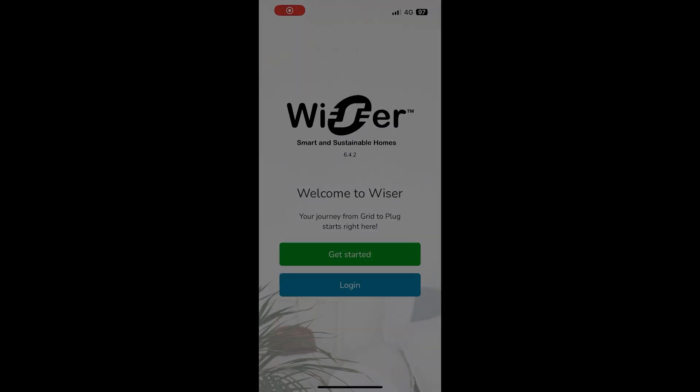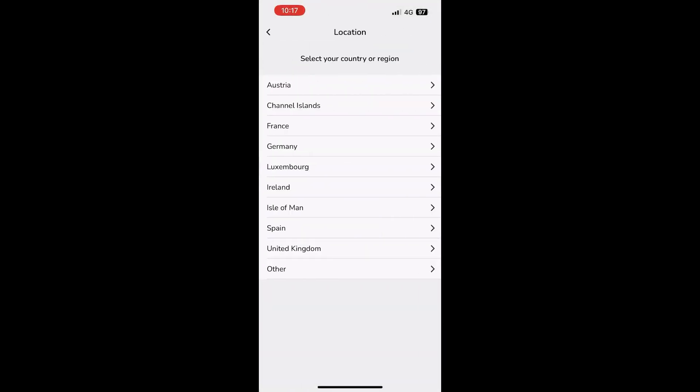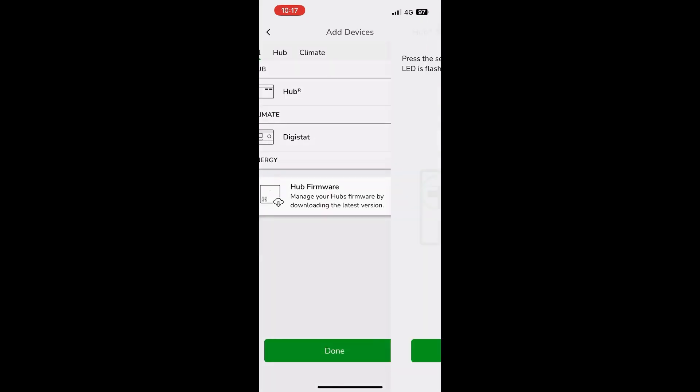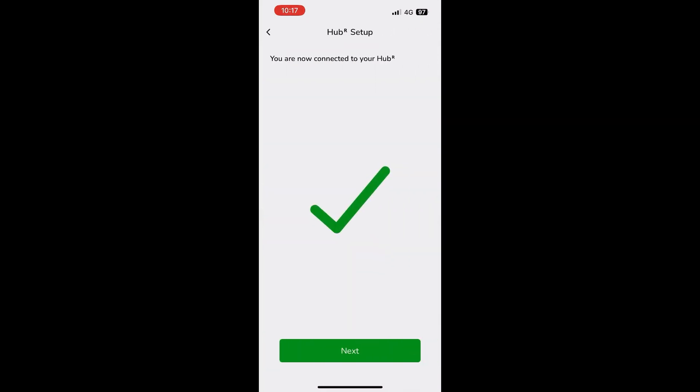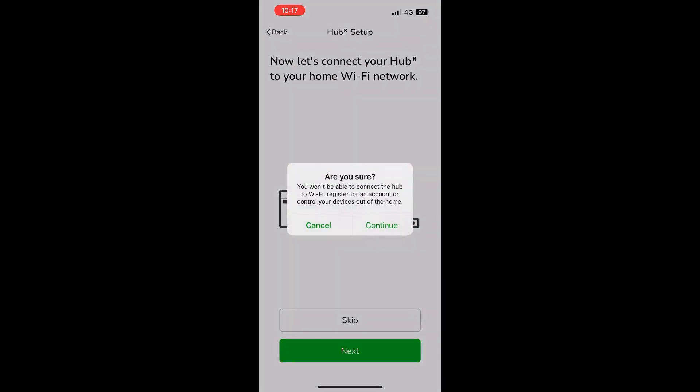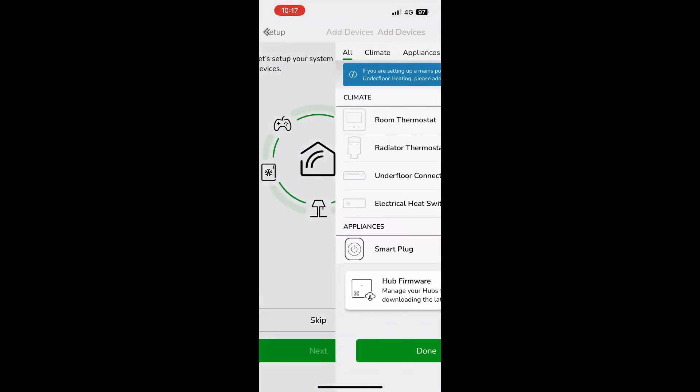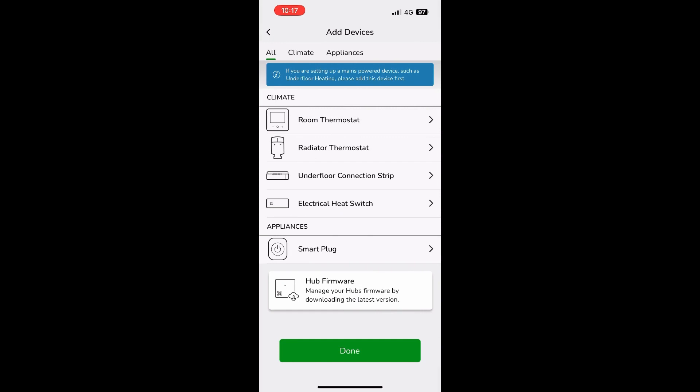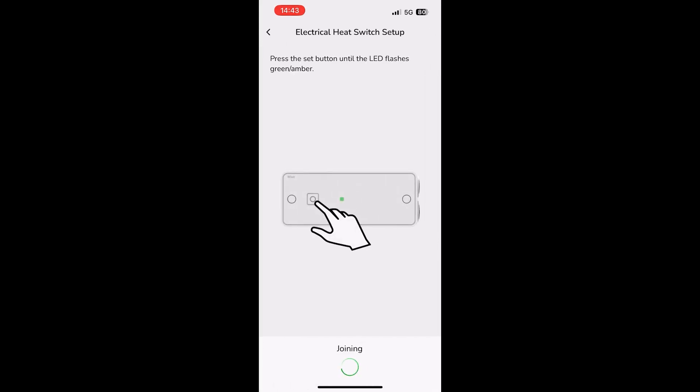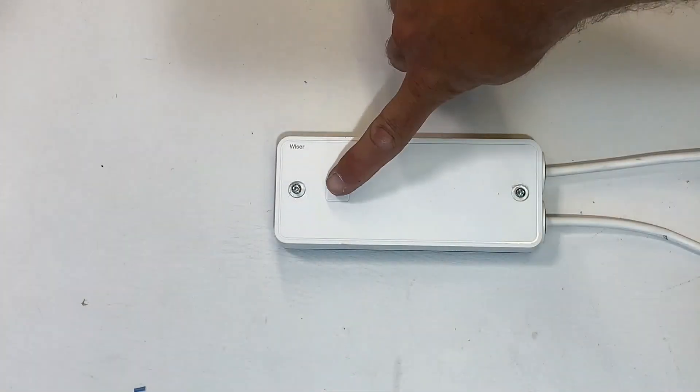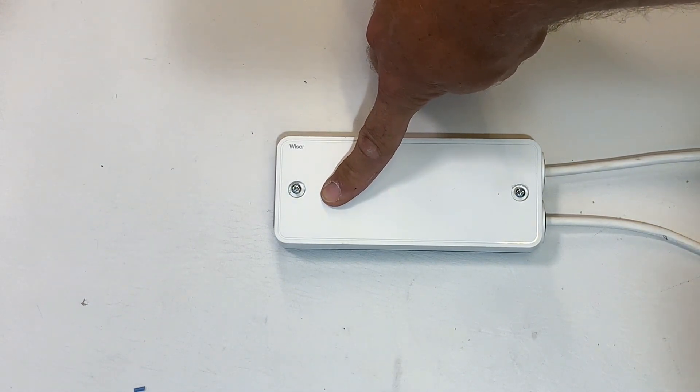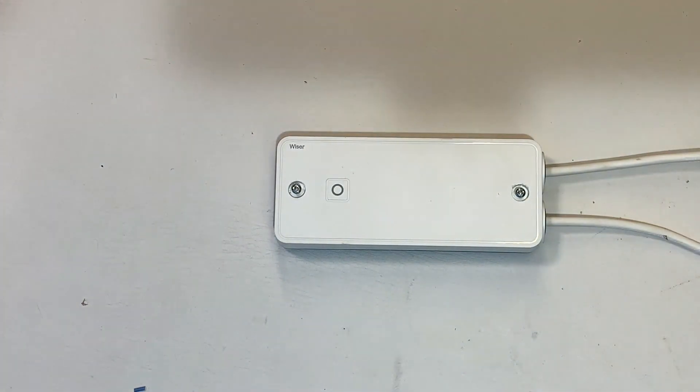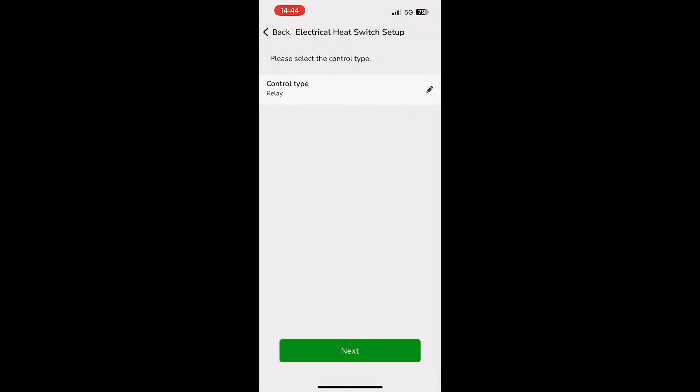Launch the Wiser Home app and click get started. Follow the professional installer route to connect your phone to the Wiser Hub R. Once connected, skip the Wi-Fi setup to get to the adding devices page. Mains powered devices always need to be added first, so start by selecting the electrical heat switch option. You are prompted to make sure that the device is wired and powered before proceeding. Clicking next will cause the hub to go into join mode. Press and hold the button on the electrical heat switch itself until it starts flashing between green and amber.